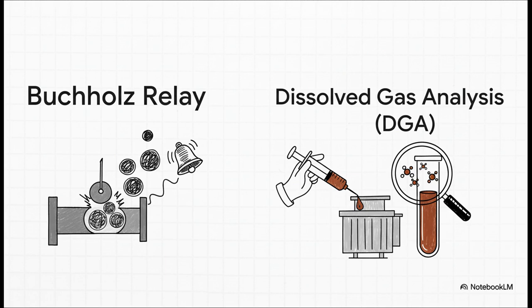And the shield doesn't just stop with electrical measurements. Oh no. We also have physical and chemical defenses. First up, you've got the Buchholz relay. It's this really clever mechanical gadget that sits in the pipe full of transformer oil. If there's an arc inside that creates a sudden gas bubble or a surge of oil, this thing physically triggers an alarm or a trip.